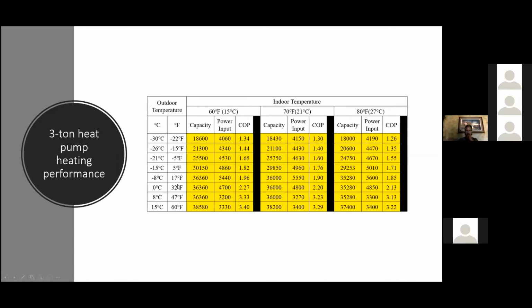So the data I took for this example: 4,800 watts to produce 36,000 BTUs with a COP of 2.2. So it still is derated to some extent at 32 degrees Fahrenheit, or 0 Celsius, but it's still more than 2.2 times the efficiency because of the way that the refrigeration cycle works for us.